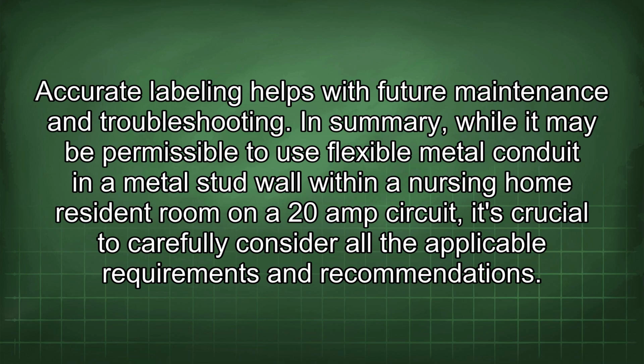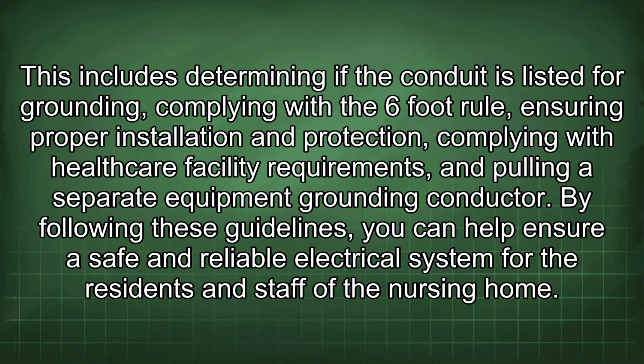In summary, while it may be permissible to use flexible metal conduit in a metal stud wall within a nursing home resident room on a 20-amp circuit, it's crucial to carefully consider all the applicable requirements and recommendations. This includes determining if the conduit is listed for grounding, complying with the 6-foot rule, ensuring proper installation and protection, complying with healthcare facility requirements, and pulling a separate equipment grounding conductor.